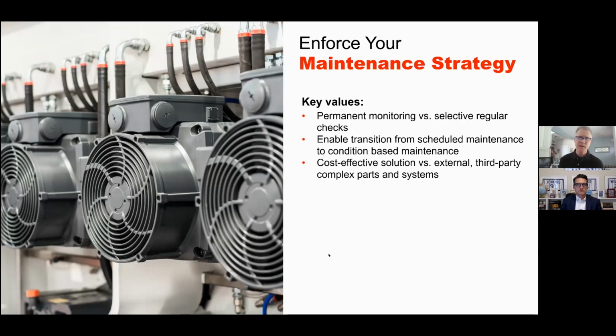Increased application uptime. If you know in advance, you're obviously going to be able to do that. Hard to get to remote locations. I mean, you could have a pump 20 foot in the air. You could have a motor 30 foot, 100 foot in the air. Some of these game parks have them 100 foot in the air, 200 foot in the air. You have to climb a ladder to go look at data on these drives if you have a problem. Wouldn't it be nice to be able to sit at your desk, take a look at your condition-based monitoring, and see where you're at, see where your failure points are, and then schedule your maintenance. I've seen people take motors off 200-foot towers with cranes. Cranes are expensive per week. We all know the expense of doing maintenance.